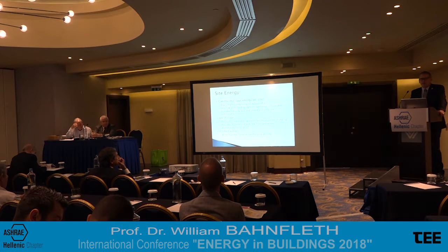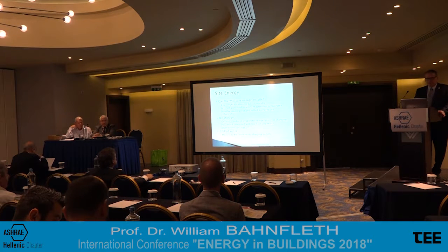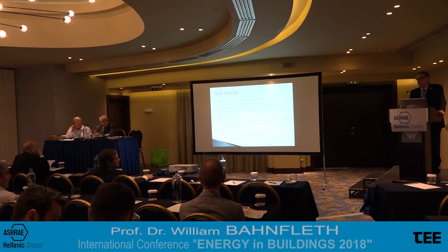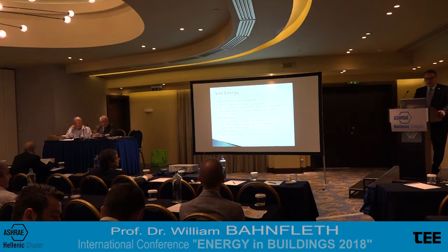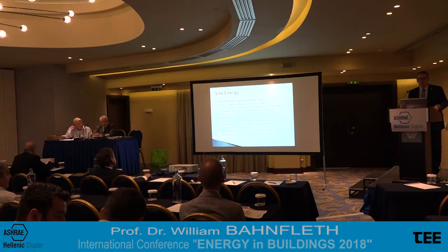So we might be talking about something that's approaching 10 degrees C difference in daytime to nighttime air-cooled condensing temperature. There's a difference for wet bulb from day to night, but it's not quite as large. So there you have to take your efficiency benefits from having a water-cooled system to begin with. So that's always going to be helpful.